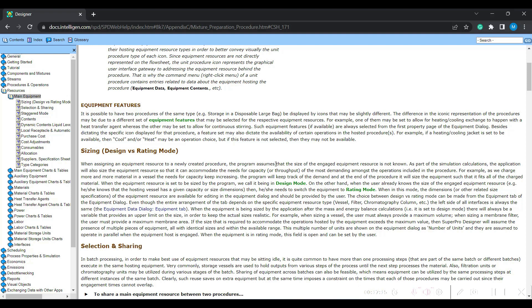The software tries to calculate the size of that particular equipment based upon the demand. In some cases, maybe a fed-batch process. For a simple batch process, equipment sizing can be easily calculated. For example, if you are using 1000 kg of media, the media density is approximately equal to water, so 1000 liters of volume is required. If only 90% of the equipment is utilized, then 1000 divided by 0.9 gives the volume required.